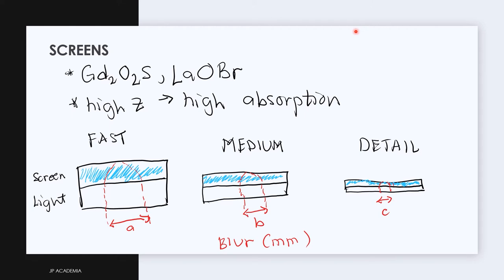On the contrary, a thin screen shown here has a low sensitivity or speed but produces a high visibility of detail due to its lower blur or lower spread shown here.